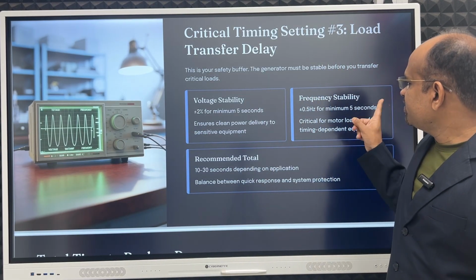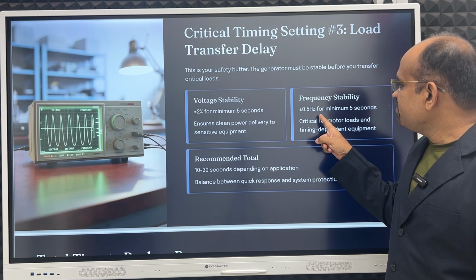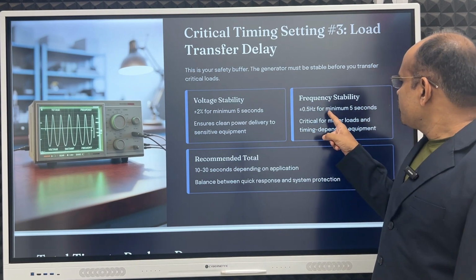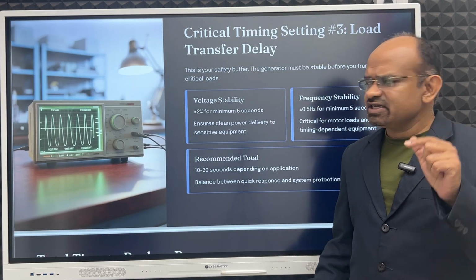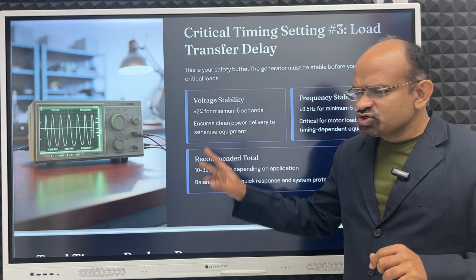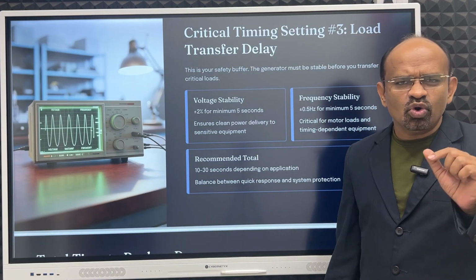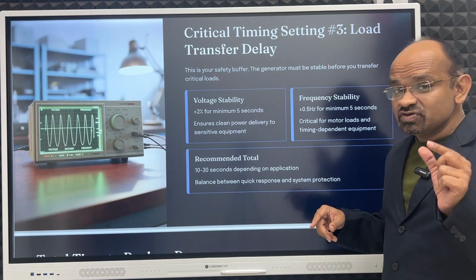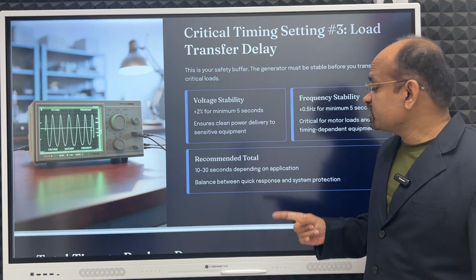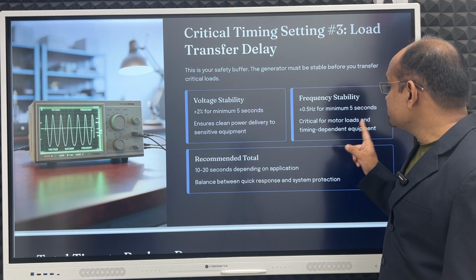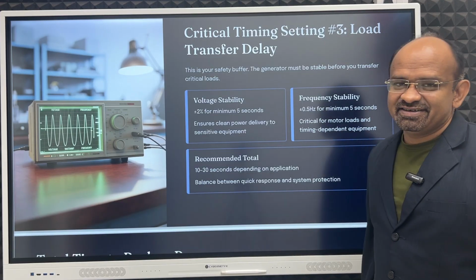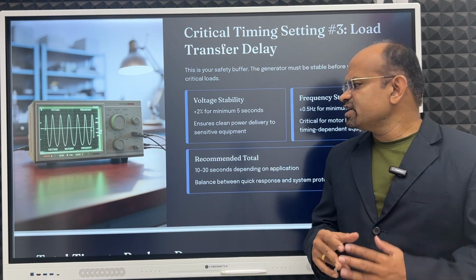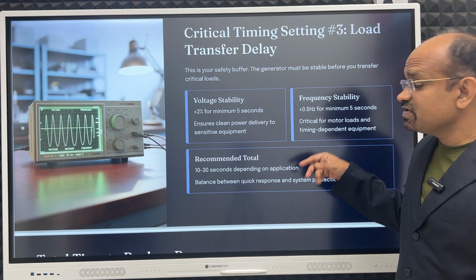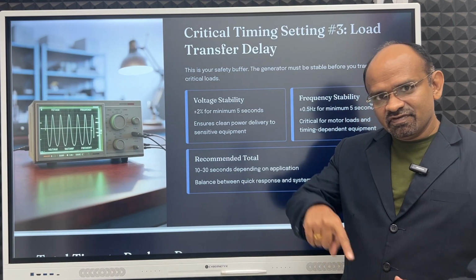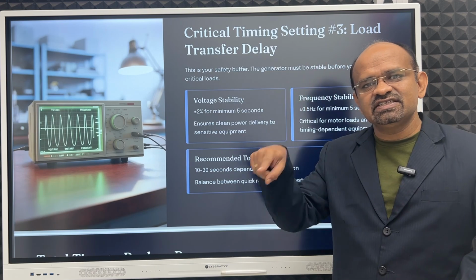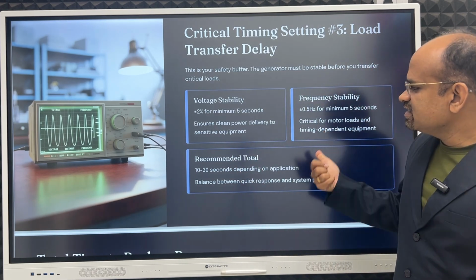Then frequency stability, plus or minus 0.5 hertz, for a minimum of 5 seconds. That much error is okay. This much, 2% and 0.5 hertz, is okay. We should check for a minimum of 5 seconds, and then we can transfer the load. It is critical for motor loads and timing dependent equipment. For motor and timing dependent equipment, frequency stability is very important. We have seen the sine wave, which changes direction in milliseconds, so this is very important.